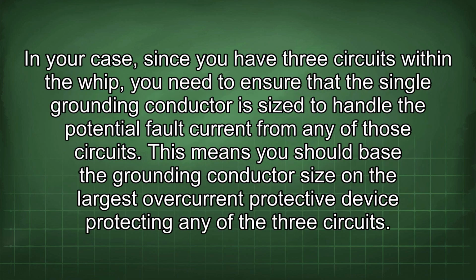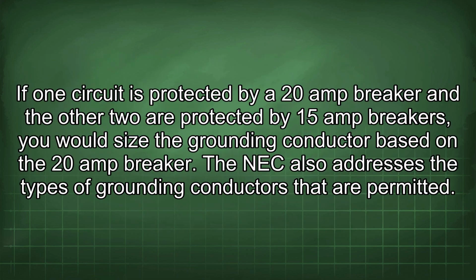In your case, since you have 3 circuits within the whip, you need to ensure that the single grounding conductor is sized to handle the potential fault current from any of those circuits. This means you should base the grounding conductor size on the largest overcurrent protective device protecting any of the 3 circuits. If one circuit is protected by a 20 amp breaker and the other 2 are protected by 15 amp breakers, you would size the grounding conductor based on the 20 amp breaker.